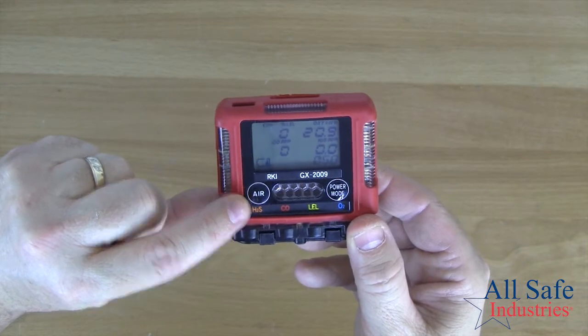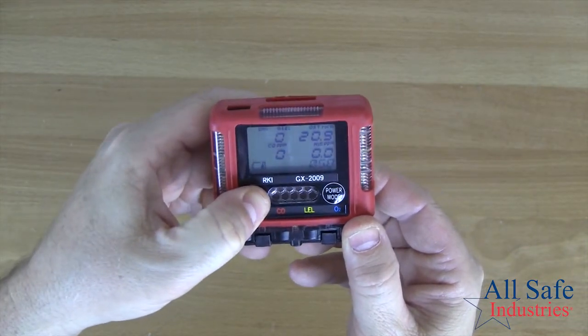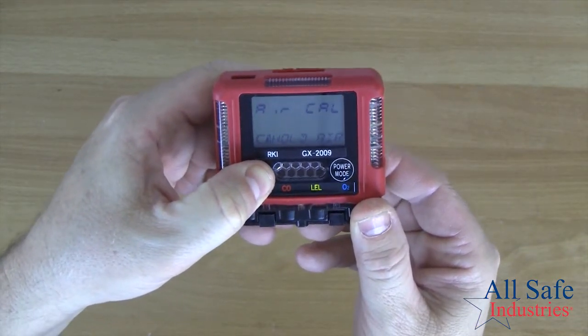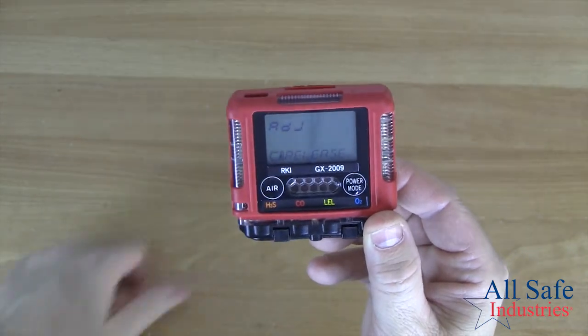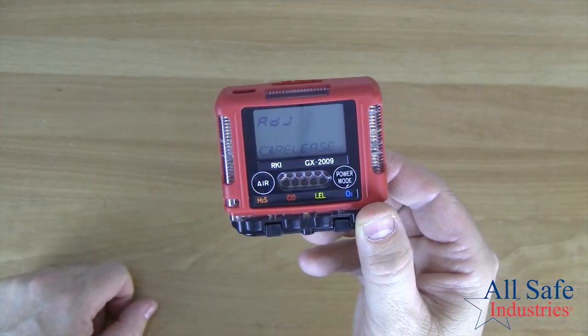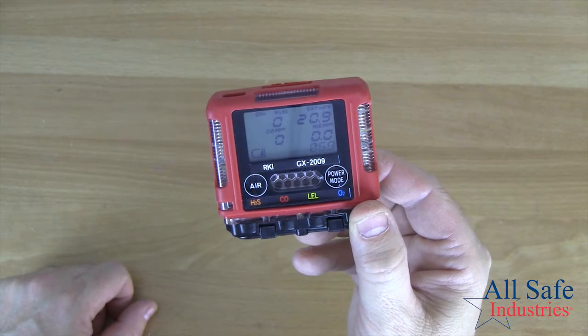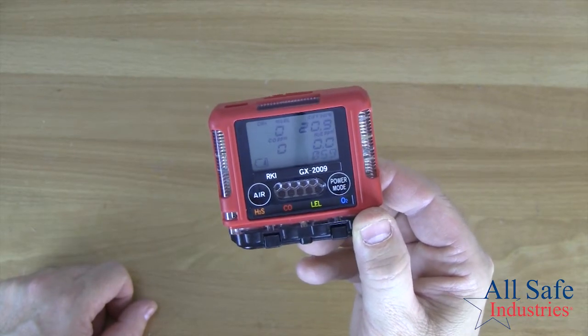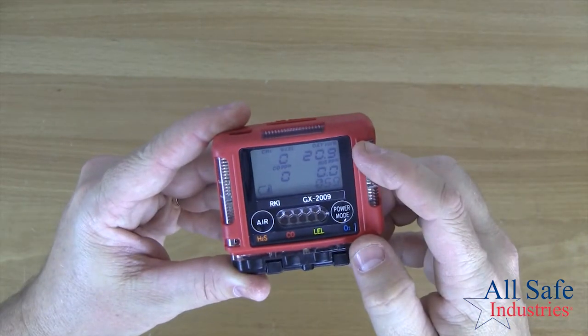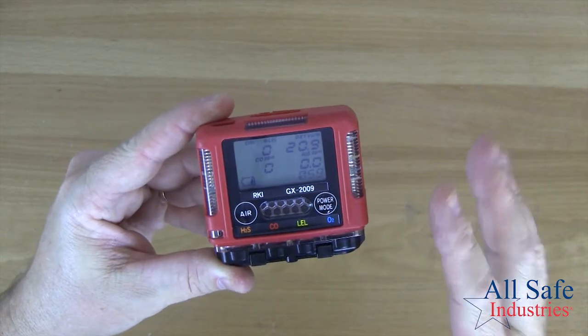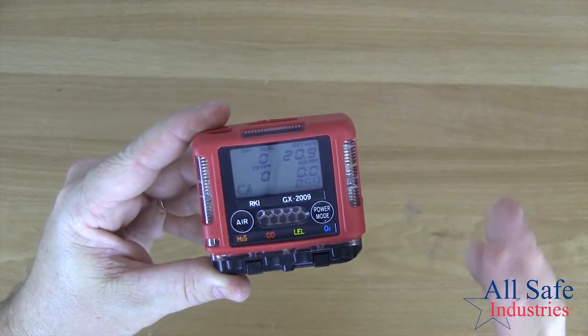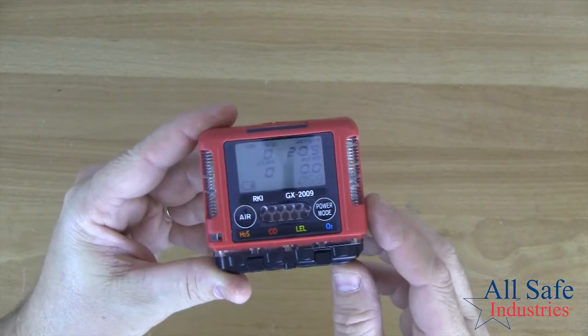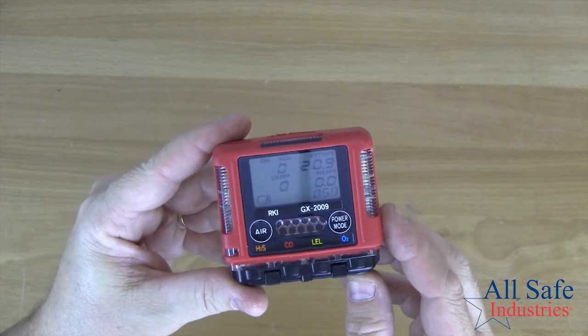It's called the air button. So you just press and hold the air button. It actually says hold air on the display, and then it will say release. Once it says release, you let go. It's going to reset all the sensors to 0, except for the oxygen sensor, which reads 20.9%. Doing a fresh air calibration is like hitting a big reset button. All the sensors reset because the instrument is trusting that you're in fresh air when you do that.